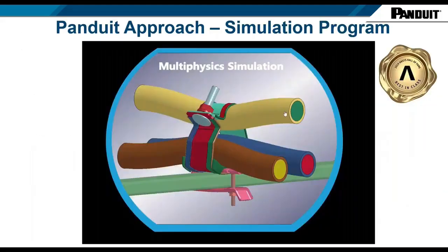What we have also developed, and we're the only company in the world that has its own software to do this. There are many different types of simulation software. Last year, or the year before, sorry, 2019, we won best in class for our development of a piece of software. A standard piece of simulation software will look at the mechanical properties of a material, and it will show you any torsion moments, it will show you the stress, strain, but it doesn't take into effect the soft jacket of the cable, the flexibility of the cable cleat, the structure that the cleat is fastened to, and all the materials within the cleat.